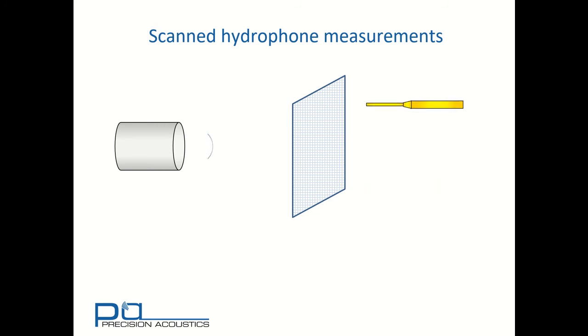We've already seen that the radiation force balance enables us to make a measurement of ultrasonic power in a few tens of seconds. Scanned hydrophone measurements are much slower. Typically, a 100 by 100 point scan can take three hours worth of measurement. So why would we incur this measurement overhead?